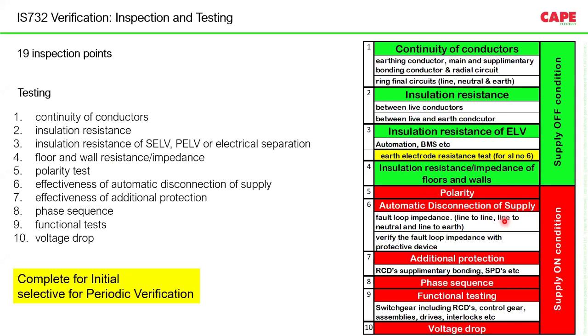Please note that out of these 10 tests, 4 tests don't require power supply; the power supply should be in off condition. And for the 6 tests, the power supply should be in on condition, meaning you need the actual power supply. Here, sometimes we face a challenge. Sometimes we go to the client before commissioning the transformer, and they say, come and do a test because now we have a temporary power supply, and we are forced to do the test with it. Actually, this is not correct. If we do the test with a temporary power supply, we really don't know what is going to happen with the actual power supply or actual transformer. So we need to do the 6 tests with the actual power supply, actual transformer, actual DG.